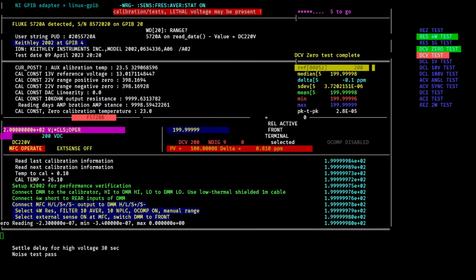So essentially, the normal procedure is to have a performance check before any adjustments, do the adjustments, and then do the performance check after the adjustment. So we have both reference as found and as returned. So the difference was only on those three in the beginning. 3 or 4, yeah. Those are the ones I'll check last.